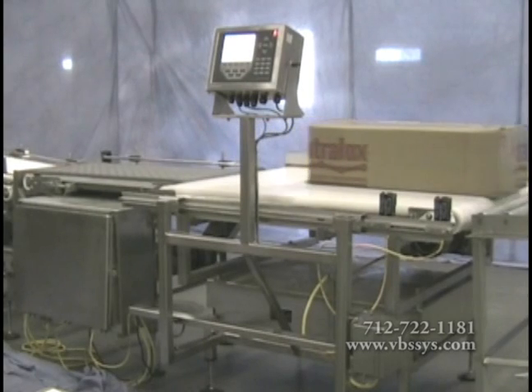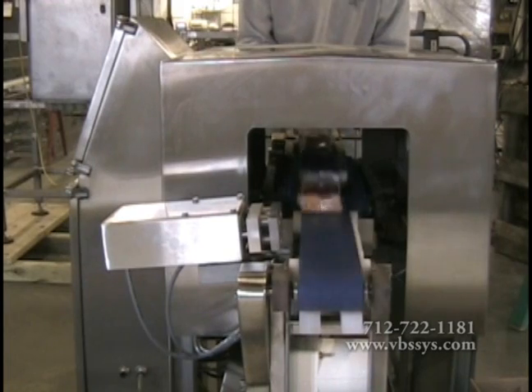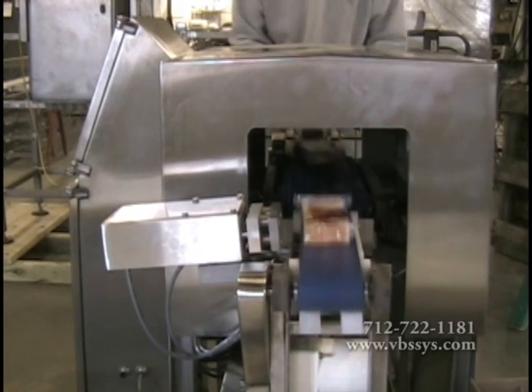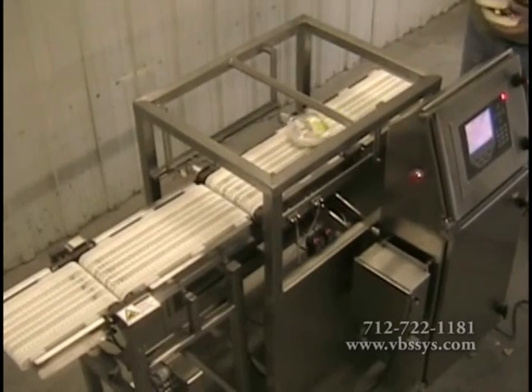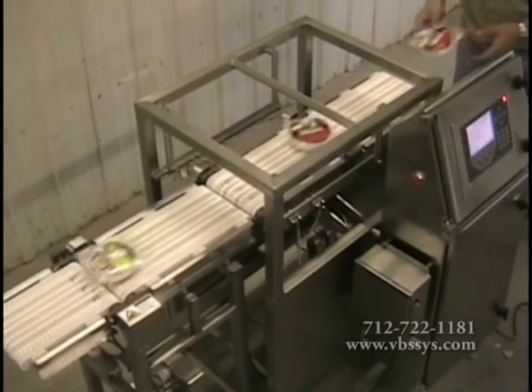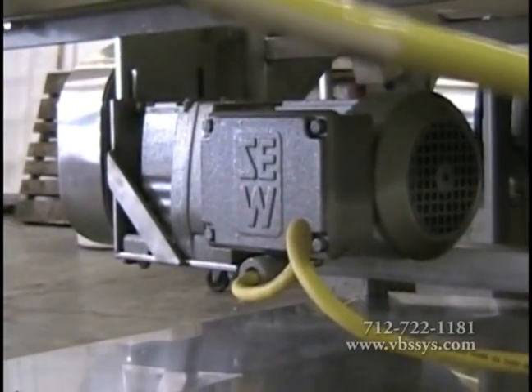Non-NTEP ranges can go further — please check with your VBS sales professional. We are always updating our processes. Belt speeds range from 0 to 380 feet per minute. We use a single load cell design for simplified maintenance, calibration, and operation. Our conveyor scale is a self-powered, isolated conveyor scale design.